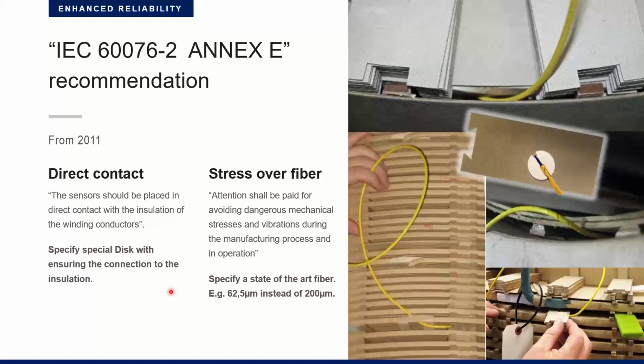or stresses over fiber. This is, from my point of view, the most important part. It says attention shall be paid to avoiding dangerous mechanical stresses and vibrations during the manufacturing processes and in operation. Because indeed, before 2011, all the suppliers were using a fiber optic wire with a 200 micrometer diameter. After the introduction of this standard, some manufacturers changed from 200 micrometer to the 62.5 micrometer fiber optic wire. And it is a standard from the telecom area.